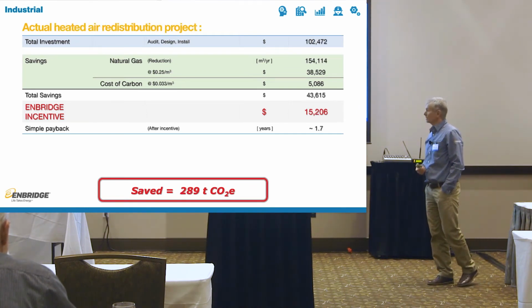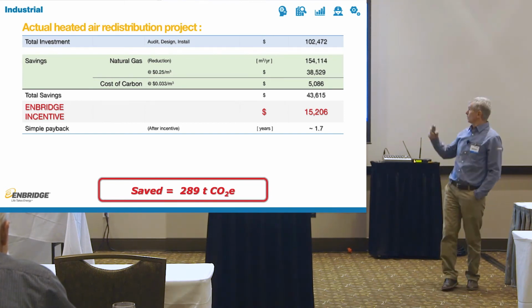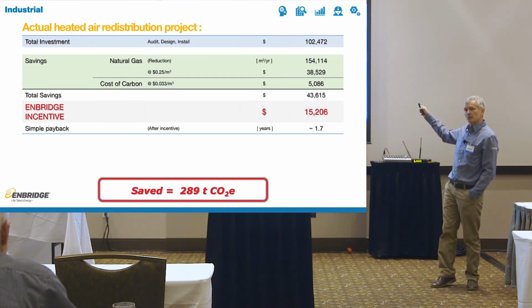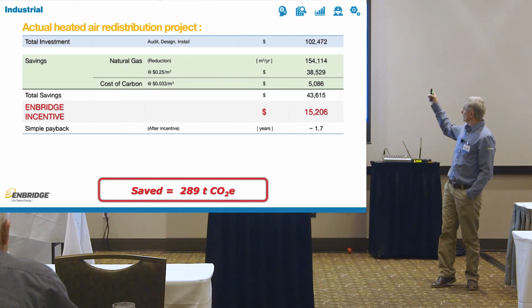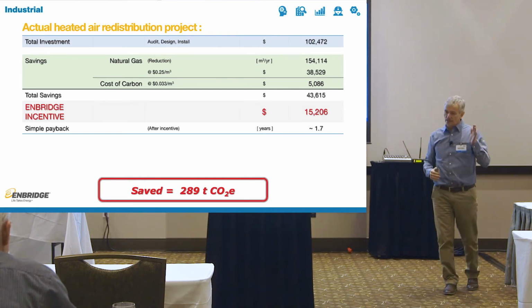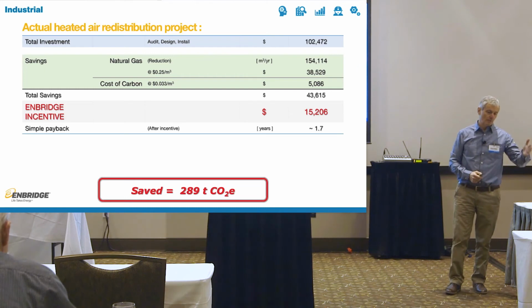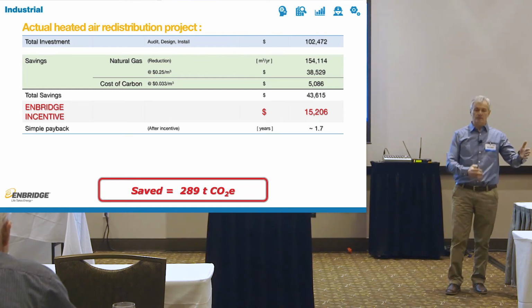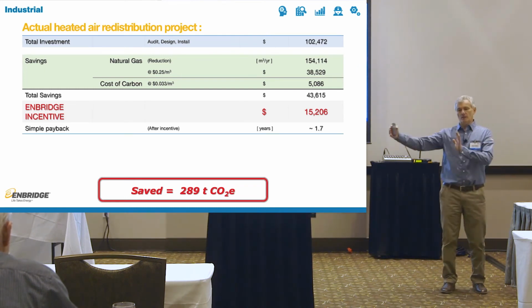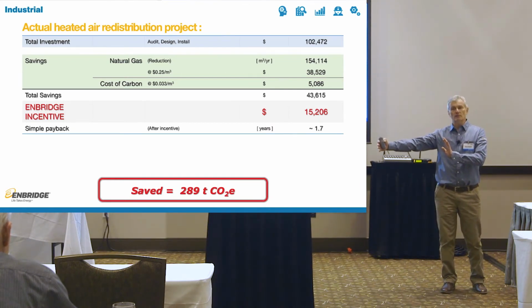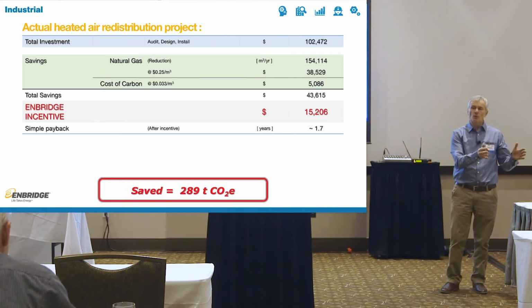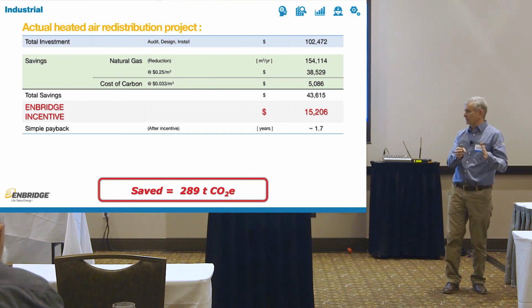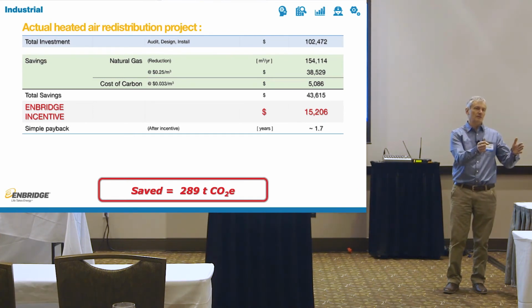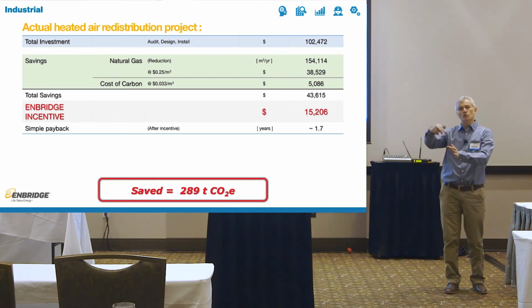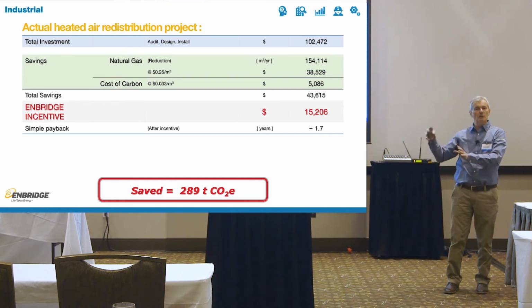Another one. This is a little more complex. So costs a little bit more, the payback, but payback is still within 2 years. These guys, for $102,000, what they had is, they had the same thing. They had the blow molding equipment on one side, then they had a big wall and a big warehouse distribution area on the other side of the wall. So here they had a whole bunch of heat. They had about, I believe it was 65 to 75,000 CFM of exhaust that was pushing that heat out. And in the warehouse, they had a whole bunch of unit heaters all around, and they couldn't keep the warehouse warm.